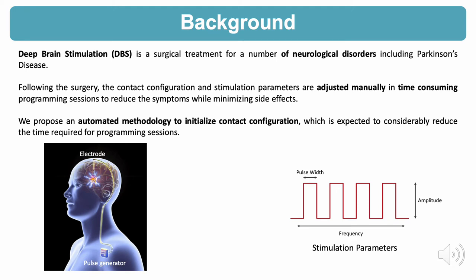There is also contact configuration. Depending on the electrode type and the number of conductive contacts it has, you can decide what percentage of the energy is to be delivered from which contact. As you can see, there are numerous possible combinations.